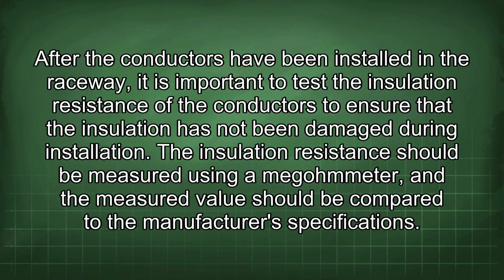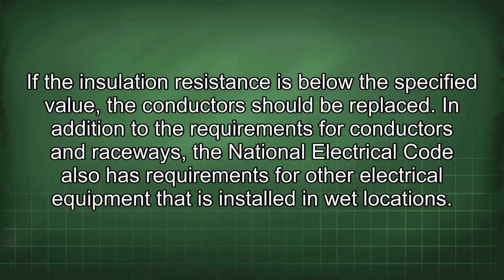the conductors. After the conductors have been installed in the raceway, it is important to test the insulation resistance of the conductors to ensure that the insulation has not been damaged during installation. The insulation resistance should be measured using a megohmmeter, and the measured value should be compared to the manufacturer's specifications. If the insulation resistance is below the specified value, the conductor should be replaced.